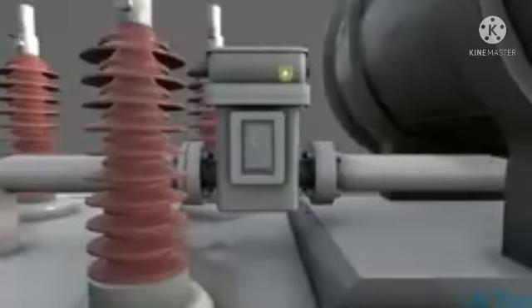Let's now have a look at one of the most important pieces of the transformer, and this is the gas actuated relay. The gas actuated relay is contained within this square box. You may also have heard the term Buchholz relay, although the Buchholz relay and the gas actuated relay are slightly different. A gas actuated relay protects against small electrical faults within the transformer and large electrical faults within the transformer. A Buchholz relay protects against small and large electrical faults, but also against a low insulating liquid scenario.